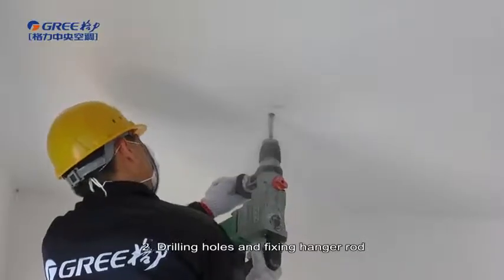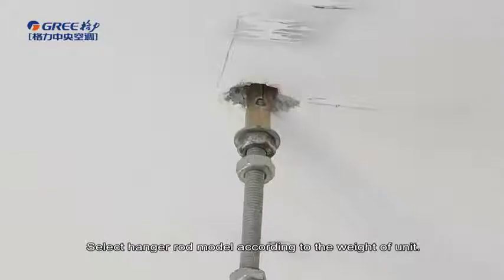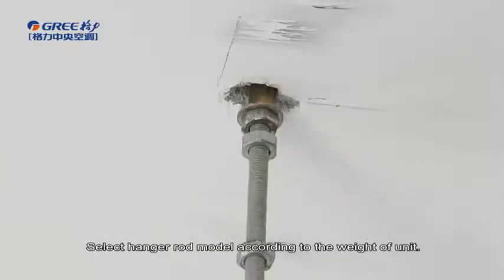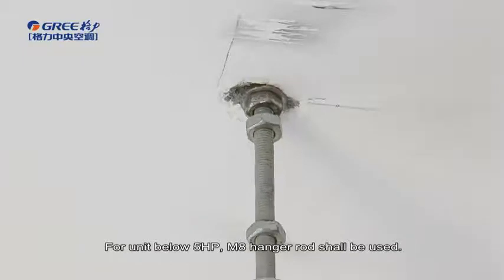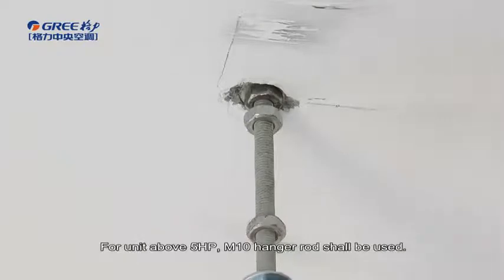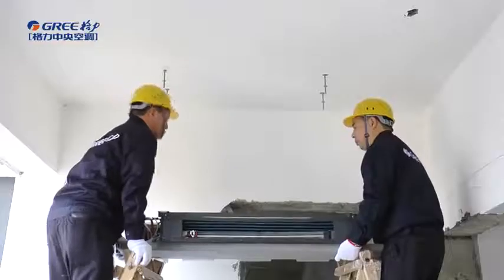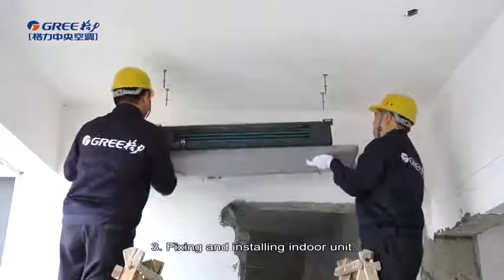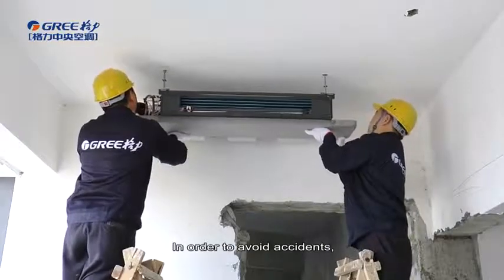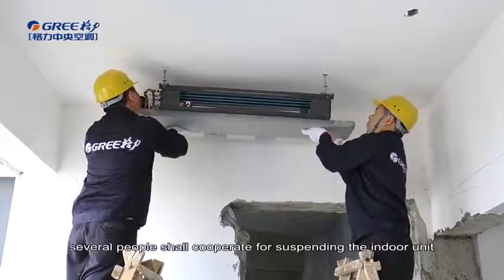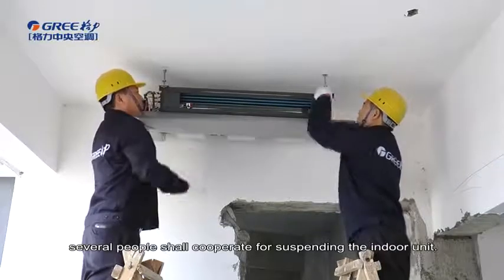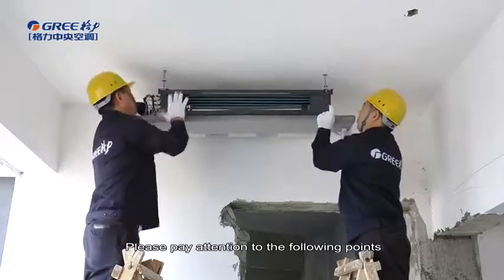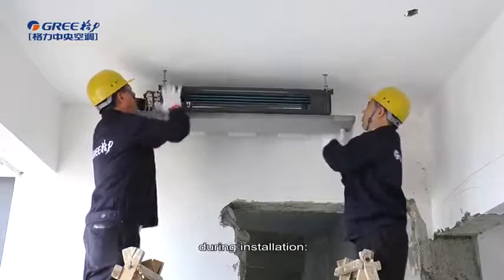Second, drilling holes and fixing hanger rod. Select hanger rod model according to the weight of the unit. For unit below 5 horsepower, M8 hanger rod shall be used. For unit above 5 horsepower, M10 hanger rod shall be used. Third, fixing and installing indoor unit. In order to avoid accidents, several people shall cooperate for suspending the indoor unit. Please pay attention to the following points during installation.